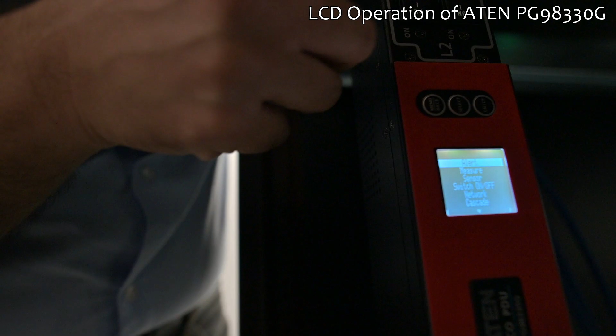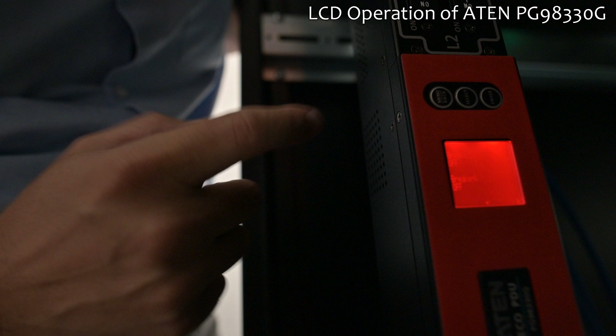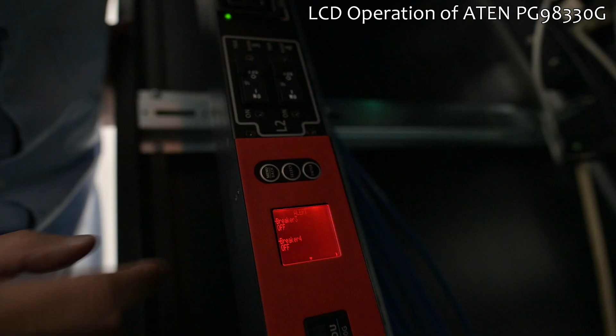This is the LCD. From here I can find out if I have alarms, and obviously I do because it's blinking red. So I press this one and I find out, reading this alarm, that I have installed a 3-phase PDU, which is this one, on just a 1-phase electric circuit.